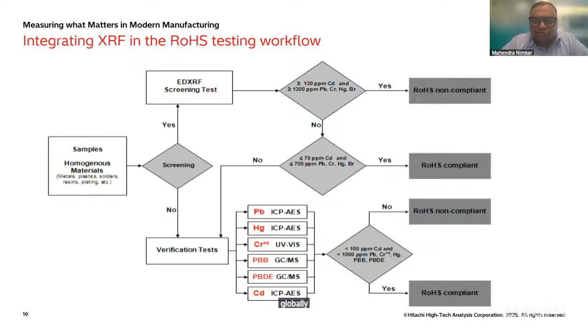So what are the benefits of XRF? I think it's very easy, very fast. You can get the results in 30 seconds, or maybe a maximum of 1 minute. It's very easy to use. There is no sample preparation. Absolutely, a layman can use the instrument. It's non-destructive, so you can keep the sample as it is. Very cost effective, and of course it is a proven technique. It has ASTM and IEC guidelines which support it, in terms of certification or guidelines, if somebody asks you which method you have used. It's also very versatile. You can test solid samples, liquid samples, paste, powder, everything with the EDXRF instrument.